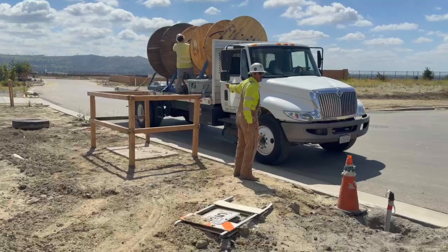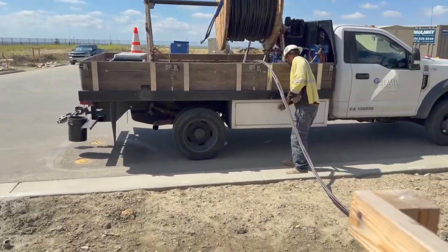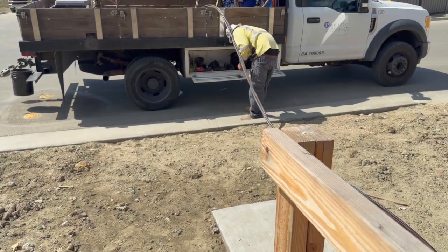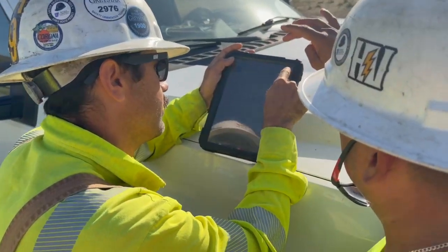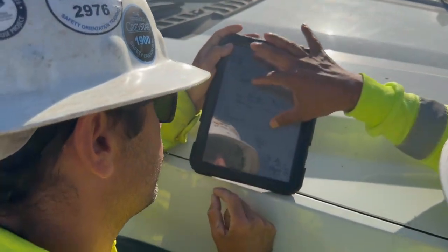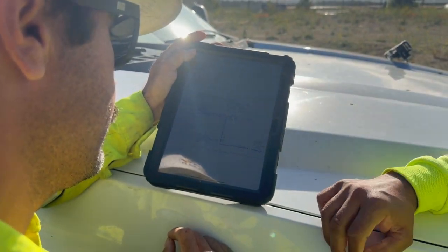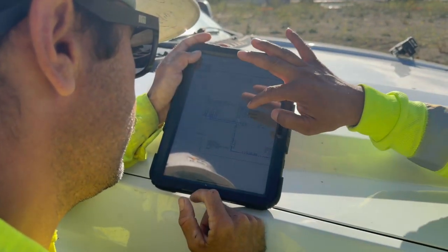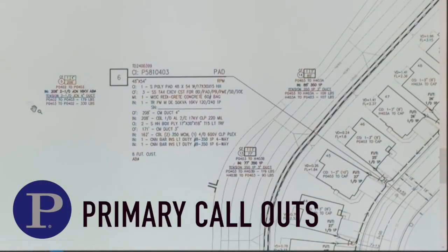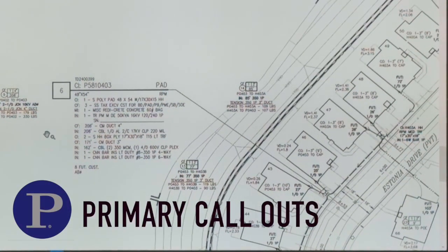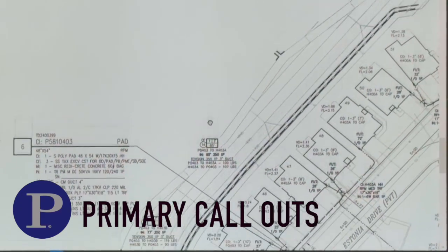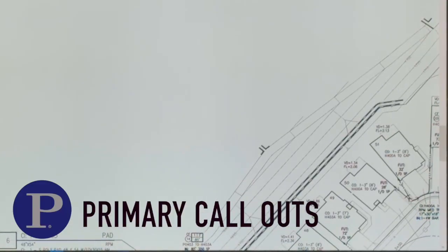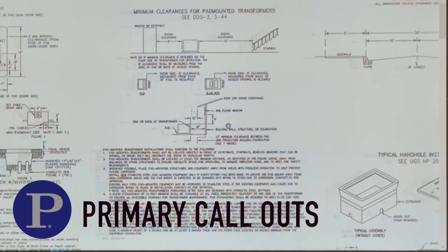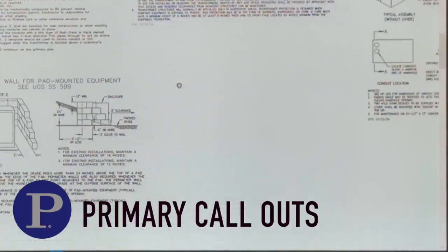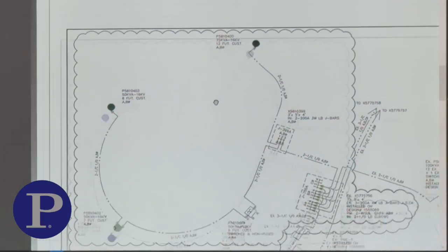Okay, first thing that you want to know when you're pulling cable is how to read a plan. If you don't know what you're putting in the ground, you're not going to be able to put it in the ground. The plan has a few things that you want to look for. These are your primary callouts. When I say primary callouts, these are your cables that will connect your pull boxes to your transformers and your other equipment such as PMEs and switches and so on and so forth.